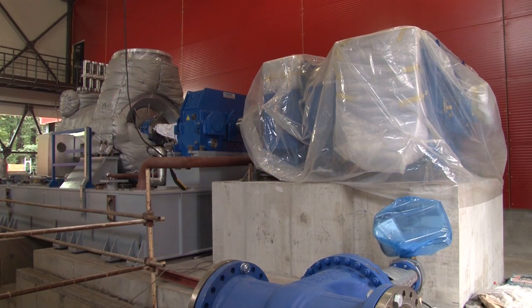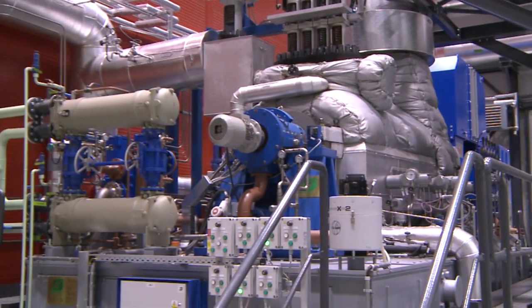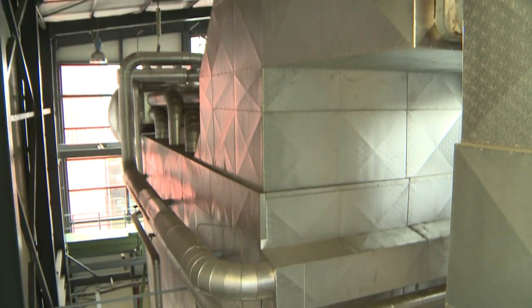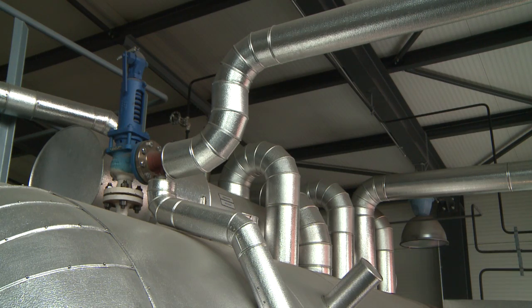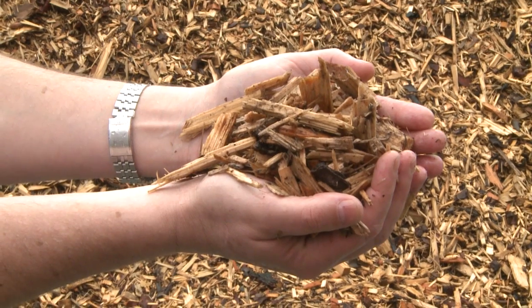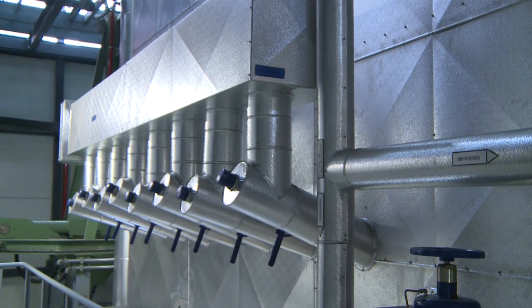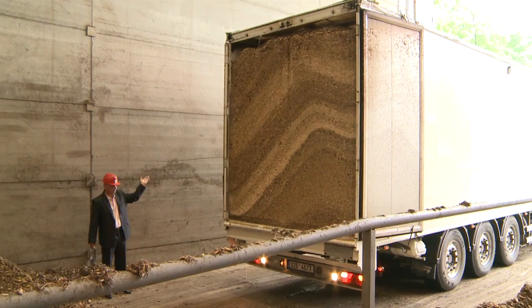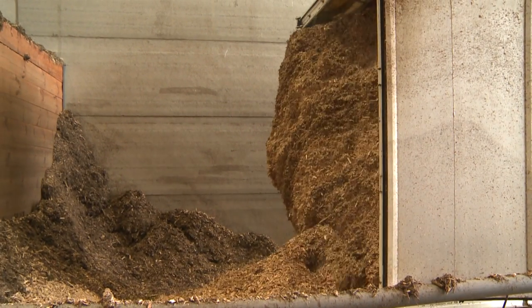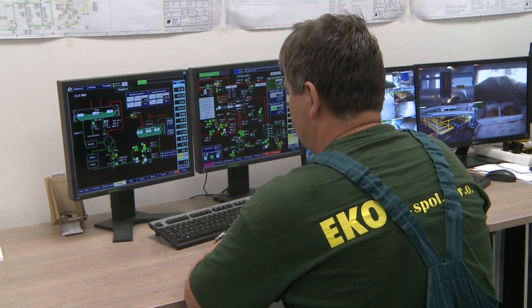An example of such a comprehensive order is the construction of the environmentally friendly bio-power plant in the premises of Friedek-Mystek's heating plant in Svyatnov — a facility for producing electricity and thermal energy. The ECOL type RKF 26 boiler is used here, which produces up to 29 tons of steam per hour. It burns biomass — wood chip to be exact. The boiler burns up to 90,000 tons of wood chip every year, transported from a covered depot by truck. All processes in the warehouse, including the grab and chip conveyor, are completely automated and can be monitored using a CCTV system from the control center.